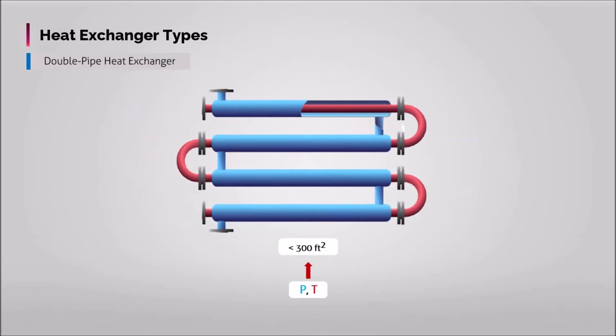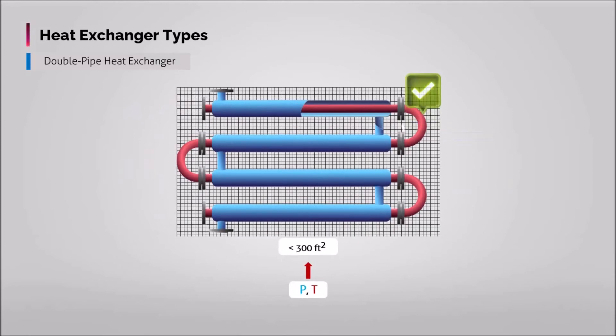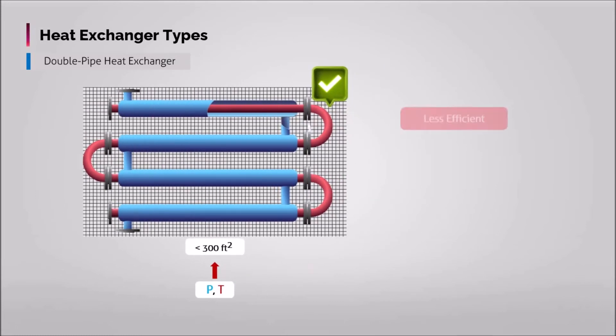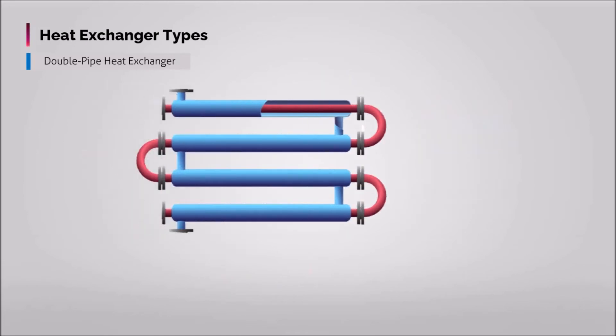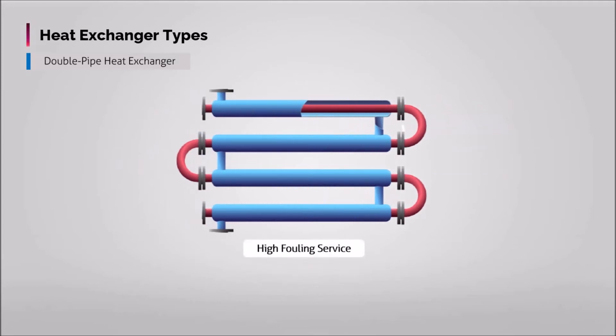Double pipe exchangers are mainly used for small duties, normally requiring less than 300 square feet, and are appropriate for high pressures and temperatures and thermally long duties due to their easily removable parts. However, in large-scale industries, double pipe exchangers are not preferred as they are less efficient, occupy more area, and have a fairly higher cost per square meter. This heat exchanger is applied generally for high fouling services such as slurries and for small heat duties.